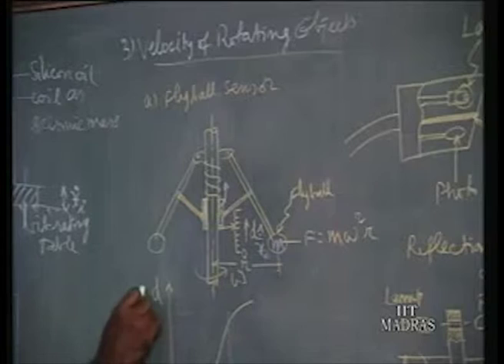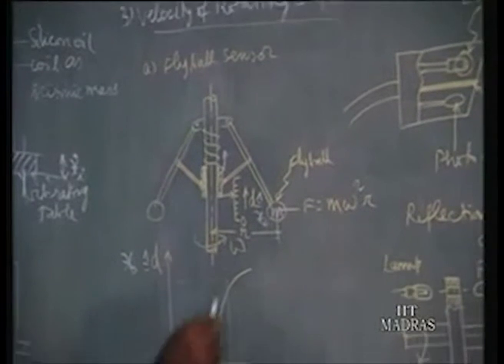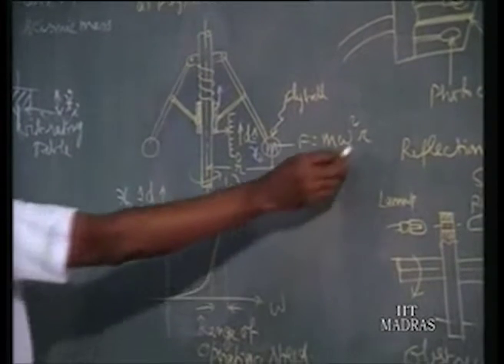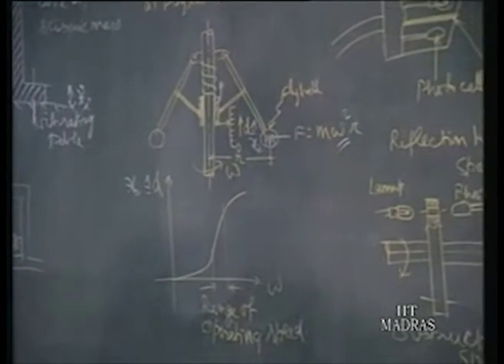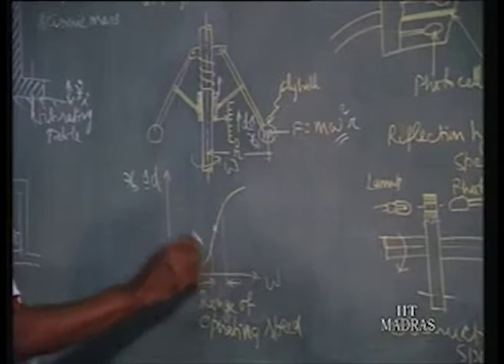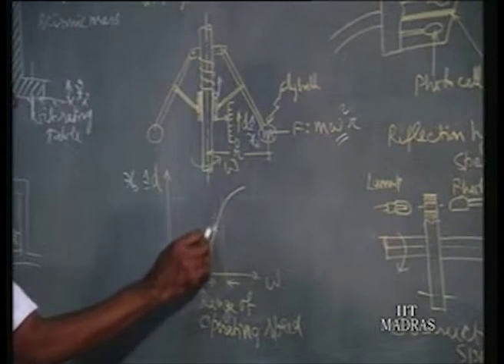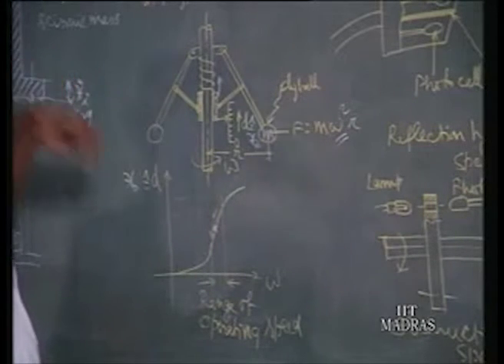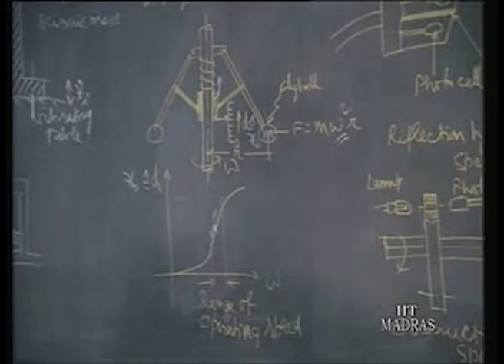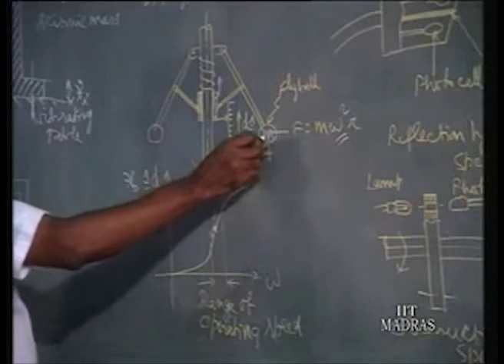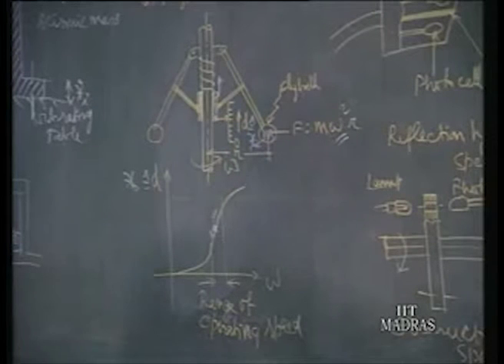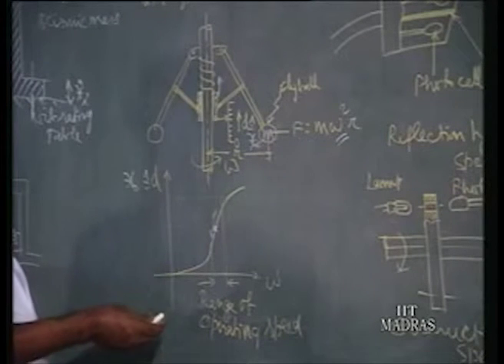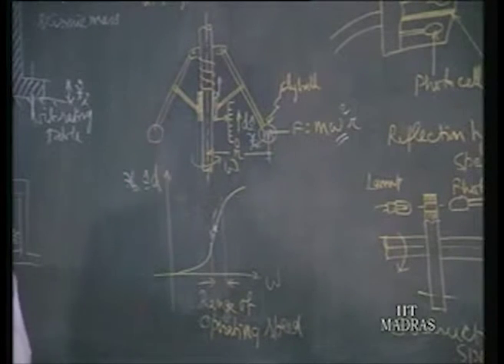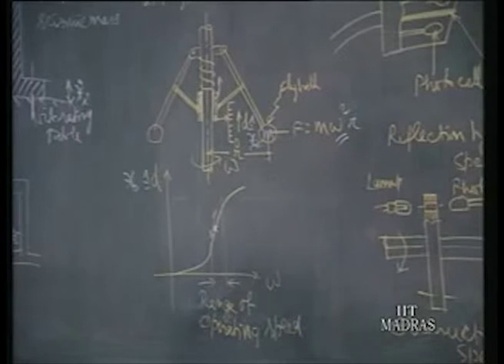Now if you plot XO versus omega, you get some nonlinear characteristics. That is because the quadratic equation comes into the picture. But the operating speed of the turbine will be somewhere in the middle of the linear portion of the curve. So, the speed will be varying along this, then immediately if speed falls down, the governor, this centrifugal mechanism, will sense it. When speed falls, this comes closer, and then some linkage will be actuated, and some more turbine steam will be taken to increase the turbine speed. That is for power plant operation, this is widely used. Still in some of the tachometers, flyball mechanisms are used, old type. This is one of the conventional methods.